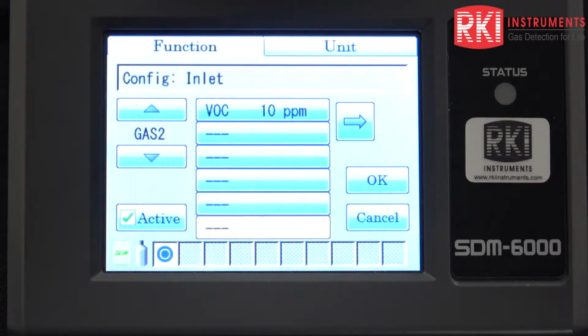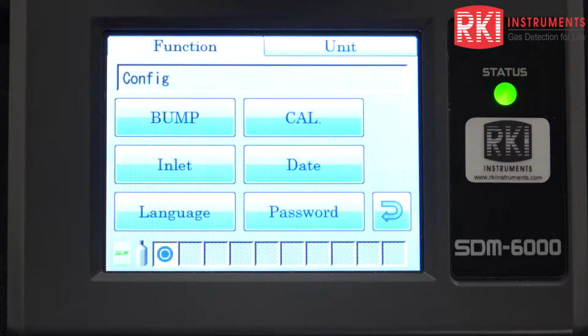So it doesn't really matter if I have gas 1 with the isobutylene and gas 2 with the 4-gas mix, as long as you make sure it matches when you set it up. And I make sure that is active and okay. So that's how you set up the inlets. It's really easy. Make sure to plug in your 6000 first because sometimes your gas will not show up. And right now we're going to quickly go over the different bump and cal parameters.